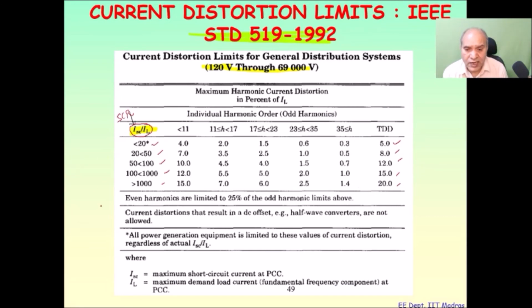And another important thing is that even harmonics are limited to 25% of the odd harmonics. You may ask, well, this is for odd harmonics, what about even harmonics? These are limited to 25% of the odd harmonics. And current distortion that results in a DC offset, such as from half-wave converters, is not allowed. So the DC component is not allowed at all. Since most of the time we have a symmetric operation of the load in terms of the waveform, DC offset is hardly present. And this is in favor of a healthy power system, that we should not have any DC offset.